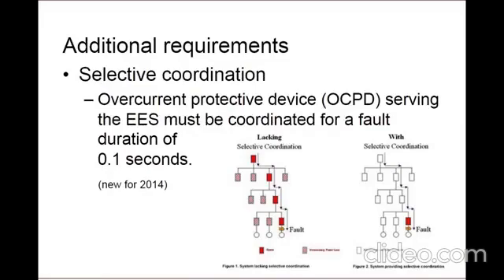And another requirement is selective coordination. A brief overview of what is meant by selective coordination is where a system is designed to help isolate a fault and not affect unnecessary equipment. So here, the diagram to the left shows a system lacking selective coordination, so there's a fault way downstream and everything highlighted in red has tripped. The system on the right is a system that has been properly coordinated and isolates the fault as close to the condition as possible, leaving the rest of the system up and running.